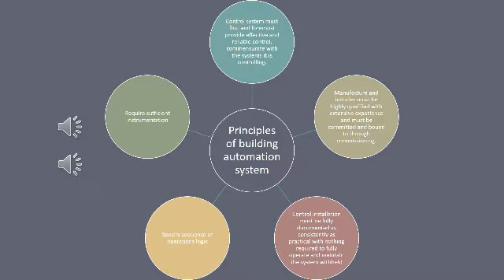Specify sequence of operation logic. The designer must know the specification and sequences of the equipment to be used in the building. Usually, the sequence of operation is already specified in general, often ambiguous terms, and the programmer of the system often resorts to sequences which are not optimal for the particular building.